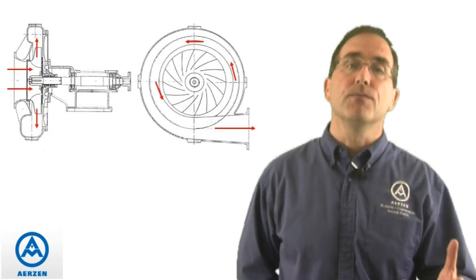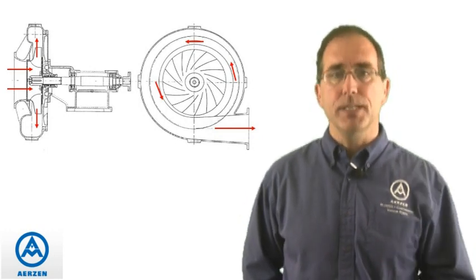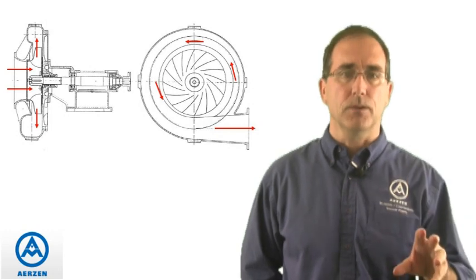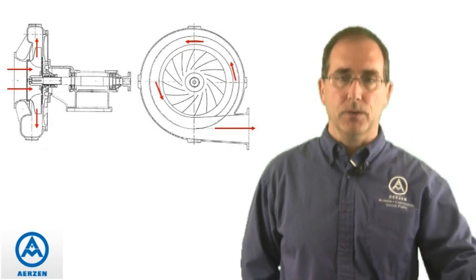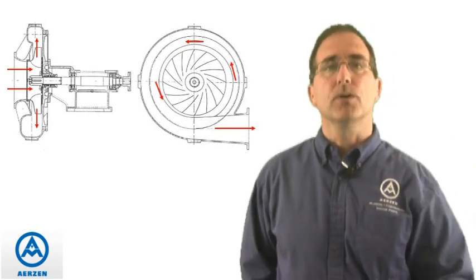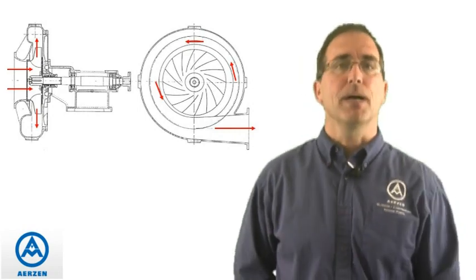The way a centrifugal compressor operates is through dynamic compression, where it converts kinetic energy into potential energy. As you can see on the diagram, the air comes in through the center of the impeller and gets flung out the outside diameter, imparting a velocity to that air, which in turn gets converted to pressurized air in the piping.